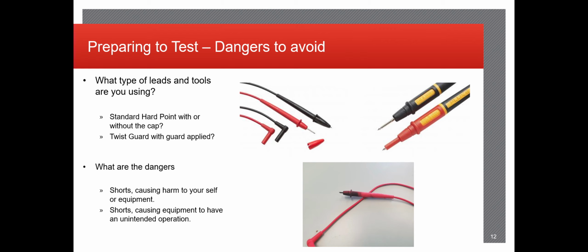Or even, if your fingers are too close to the end of those test leads and you touched it and tried measuring power, you might get shocked too. And the example down below is one with what seems like a very exposed test lead that has burn marks on it, meaning that there was probably a short, and quite possibly the lead might even have been longer.